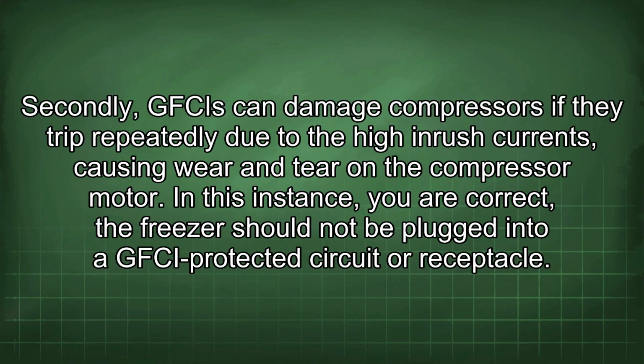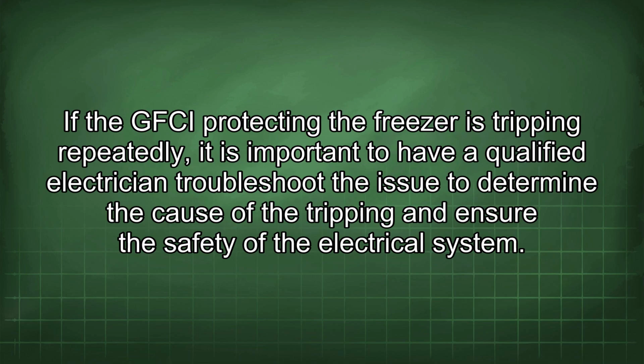Secondly, GFCIs can damage compressors if they trip repeatedly due to the high inrush currents, causing wear and tear on the compressor motor. In this instance, you are correct, the freezer should not be plugged into a GFCI protected circuit or receptacle. If the GFCI protecting the freezer is tripping repeatedly, it is important to have a qualified electrician troubleshoot the issue to determine the cause of the tripping and ensure the safety of the electrical system.